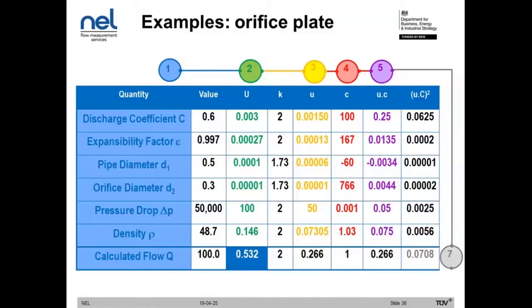Once you have the sensitivity coefficient and the standard uncertainty, we combine those to get the overall component uncertainty. So in the purple column, we have the combined sensitivity coefficient and standard uncertainty for each of the input uncertainties. Now, we want to combine each of those, and they are uncorrelated, so what we do is perform the root sum squared method. So the very last column in the table, we're taking the previous value under the purple column, and we're squaring it.